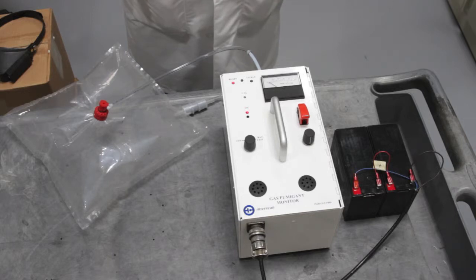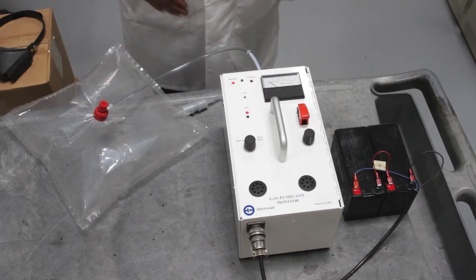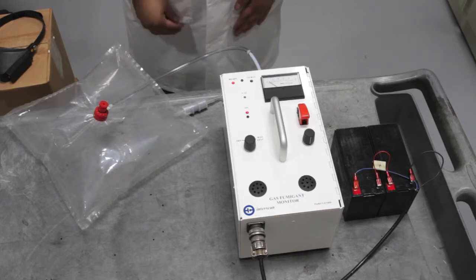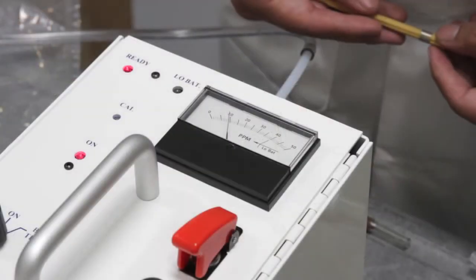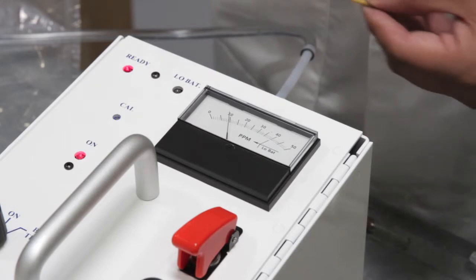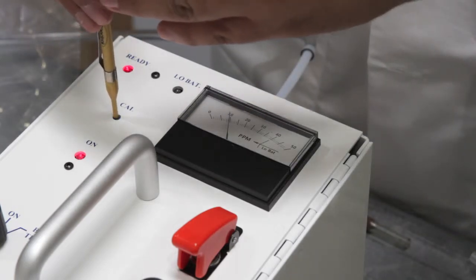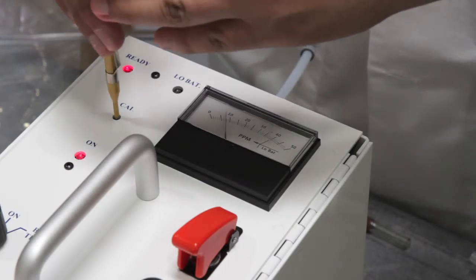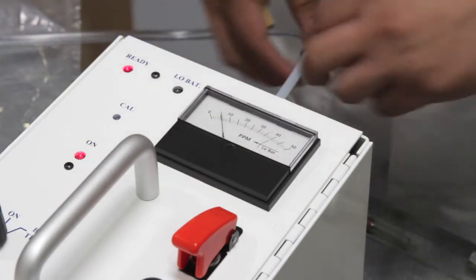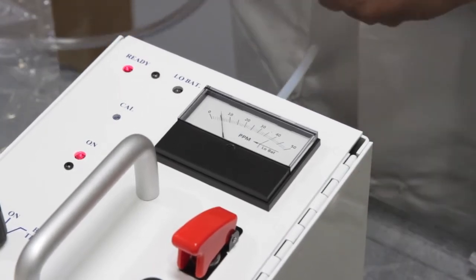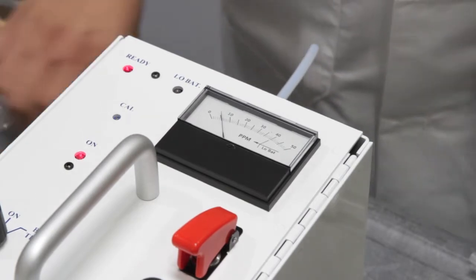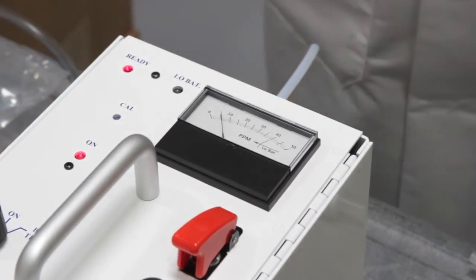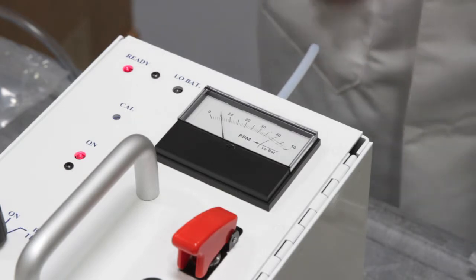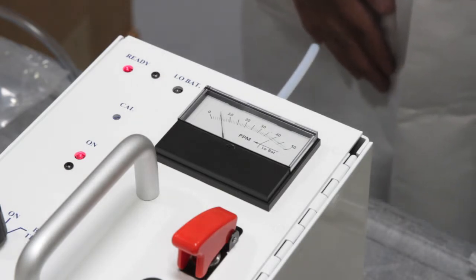Never attempt to introduce a gas standard directly from a pressurized source. A sample bag must always be used. Also, never introduce concentrations higher than 50 parts per million. The cal control is used to set the meter to a value corresponding to the span gas concentration. Disconnect the sample bag. Allow the monitor reading to stabilize for 3 minutes. Then repeat the procedure 2 additional times.